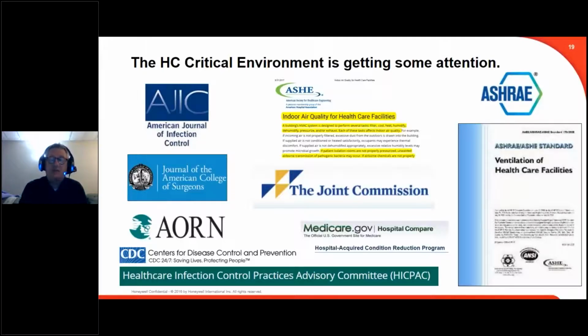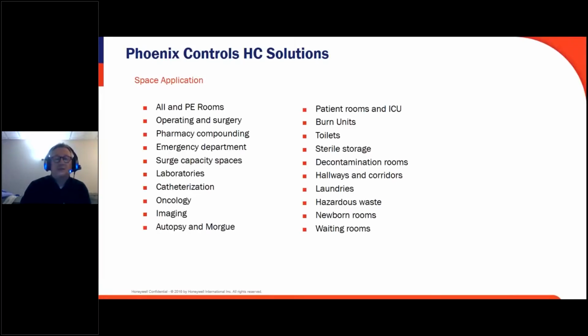And when I talk about critical care spaces, I'm talking not just necessarily about what goes on with the patient, but just the need for pressurized space, in order to manage particulate or quality of air, but also just the air change rates, right? If you have higher than normal air change rates, anything above 4 or 6, there's something going on in that space that's critical or that impacts the effect on the patient and the safety of that staff, right? And so these are a number of different spaces that are being looked at, and some that you may not have heard of, right? I mean, obviously laundry areas, hazardous waste areas, NICUs, ICUs, even emergency departments right now are being looked at to maintain a better directional flow in order to keep that space cleaner to reduce their infection risk. And this is something I feel that we as the US are a little behind on.